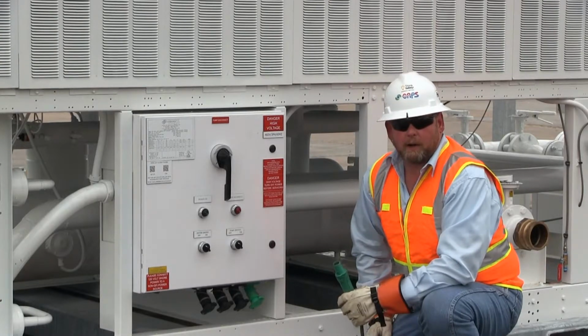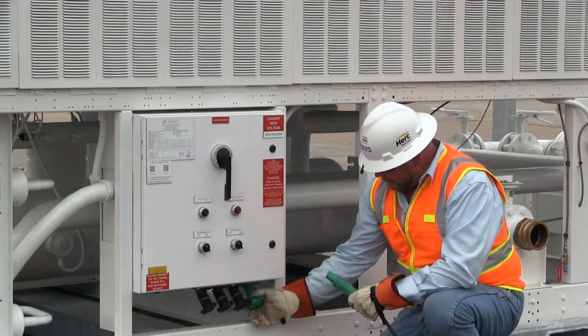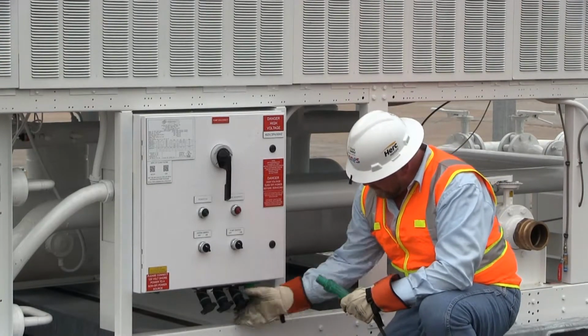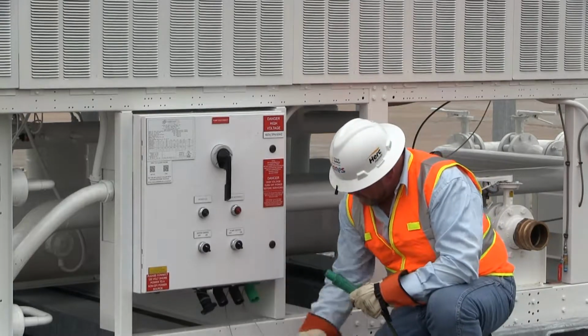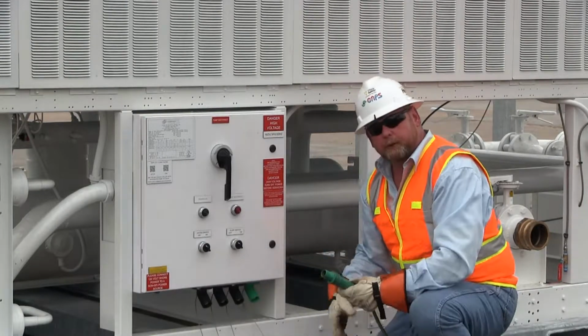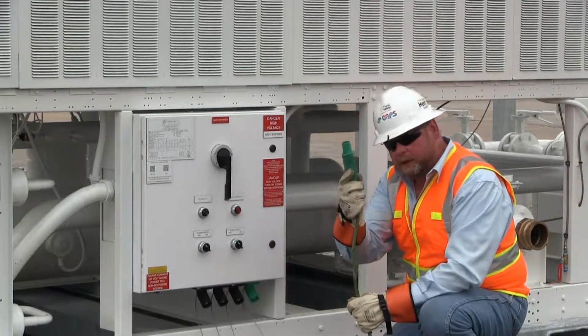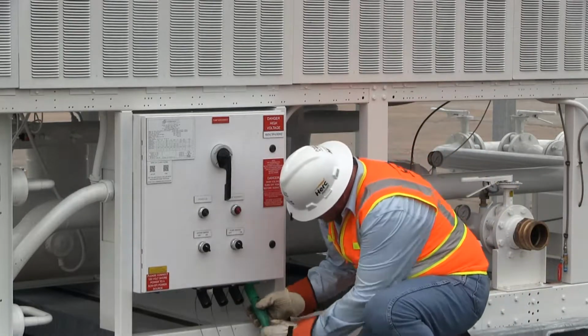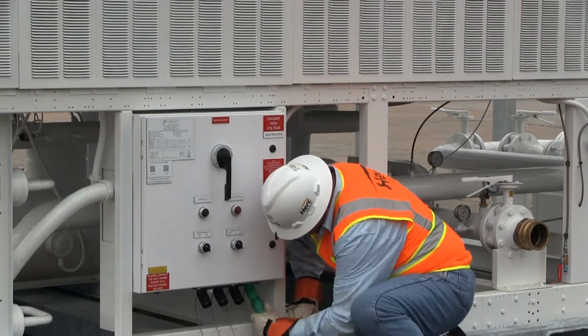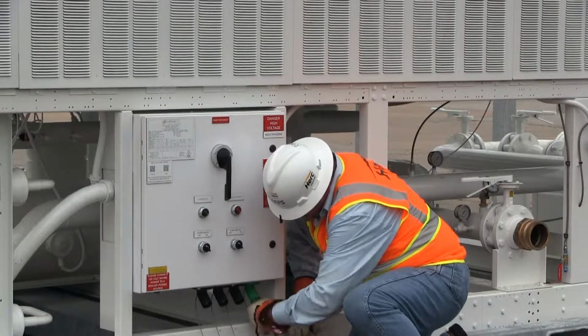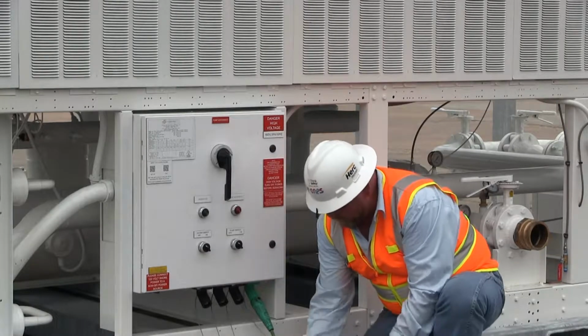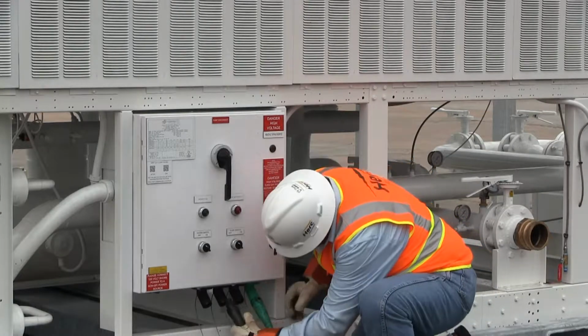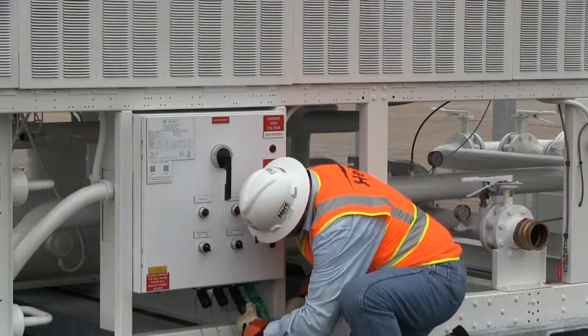Now that we know our power requirements, it's time to hook up the power. We're going to remove the moisture and dust seals from the cam locks. That's for ground, L1, L2, and L3. You're always going to hook up your ground cable first. We want to make sure that we've got a good ground to the chassis or to the earth before we start hooking up our L1, 2, and 3. Then we'll proceed with hooking up each of the lines.